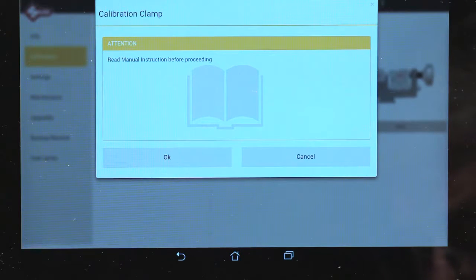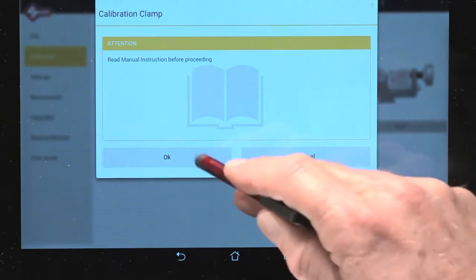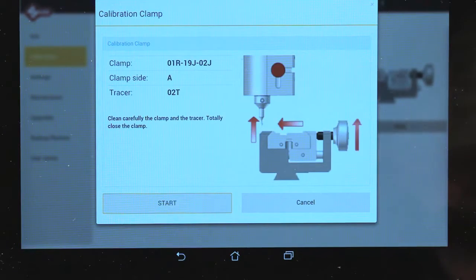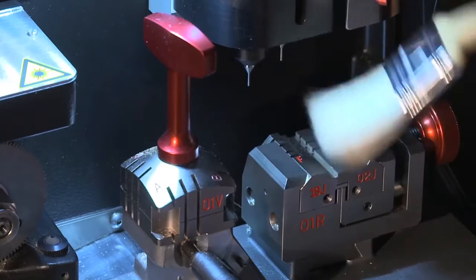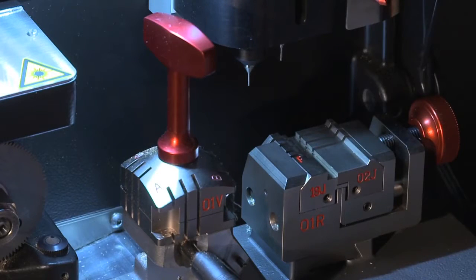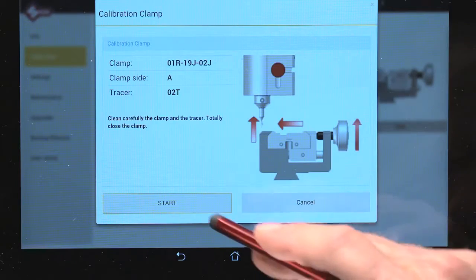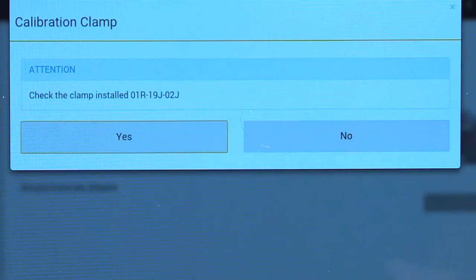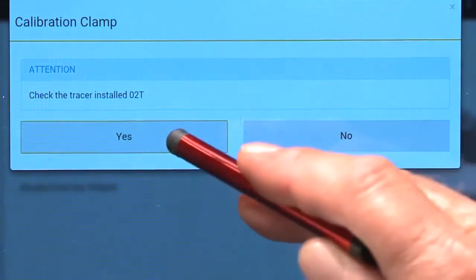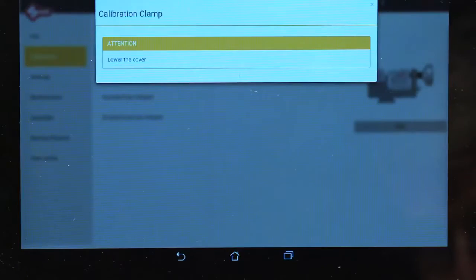You will receive a reminder to read the instruction manual before proceeding. Once you've reviewed the instructions, select OK. The next screen verifies the specific clamp jaw combination to be calibrated. Since the machine uses electrical contact for calibration of these jaws, you need to carefully clean the clamp and tracer before you begin the process. Select Start to begin the calibration. Select Yes to confirm jaw combination. Select Yes to confirm 02 tracer is installed, then press Start.